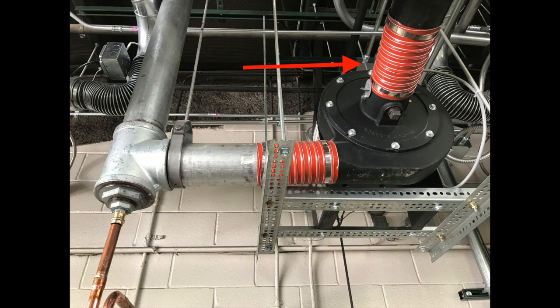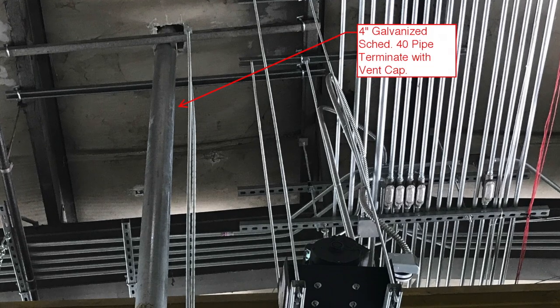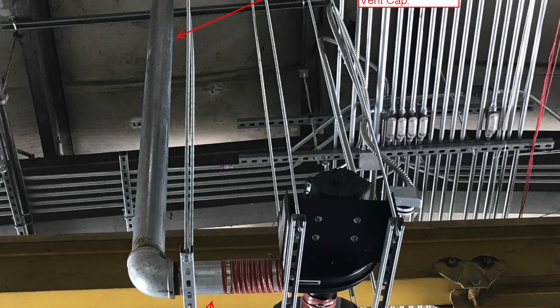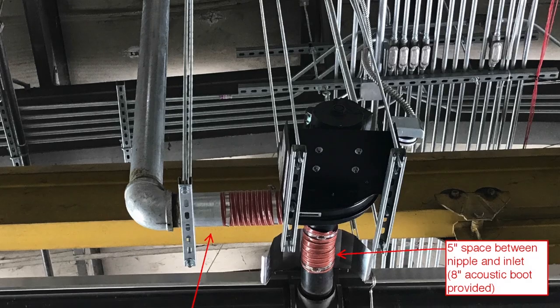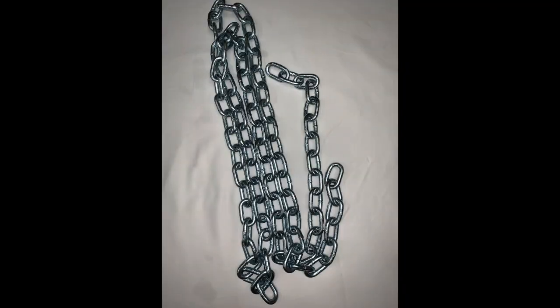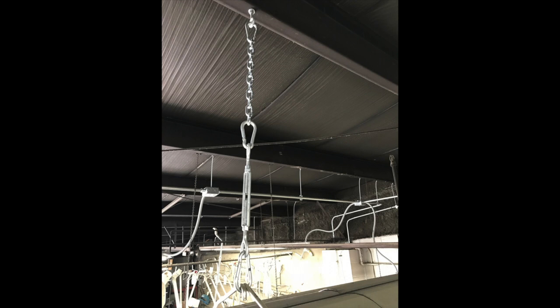When the Schedule 40 pipe reaches the vacuum pump, it needs to be 4 to 5 inches short in order to accommodate the boot that is in place to absorb the vibration from the vacuum pump. The hangers are suspended from the building purlins. The hangers are attached via 3/8 eye bolts, spring hooks, and turnbuckles, along with the appropriate length of chain to hang the system at the desired height. If needed, you, the mechanical contractor, will provide unistrut for all bridging.